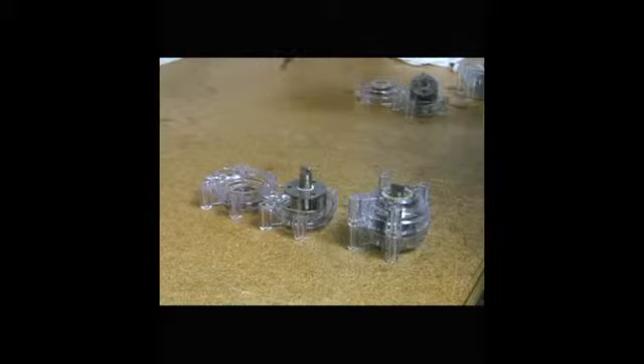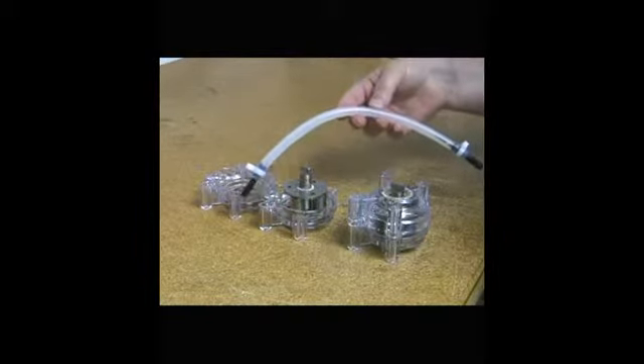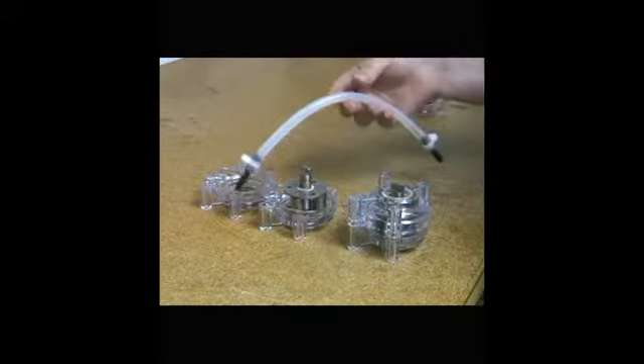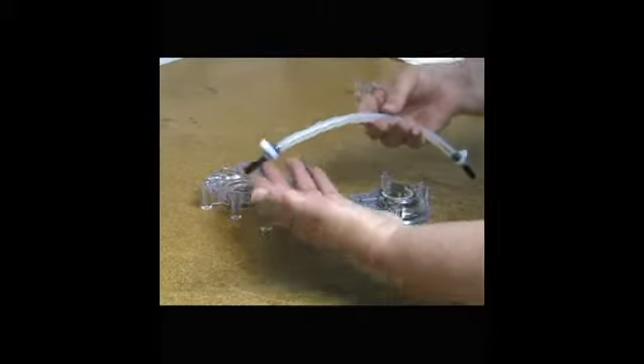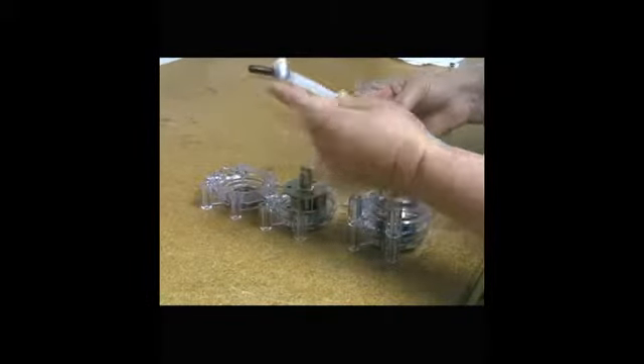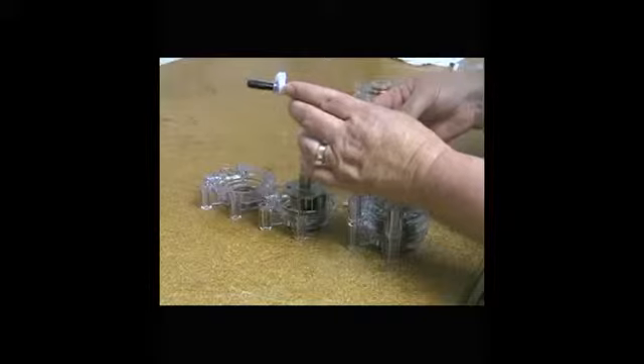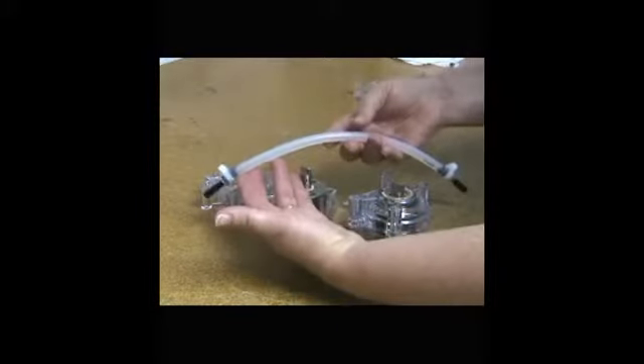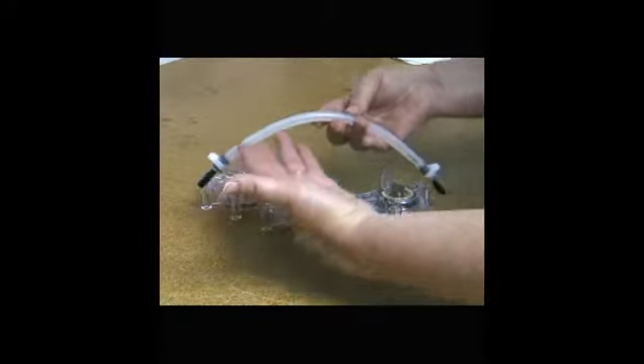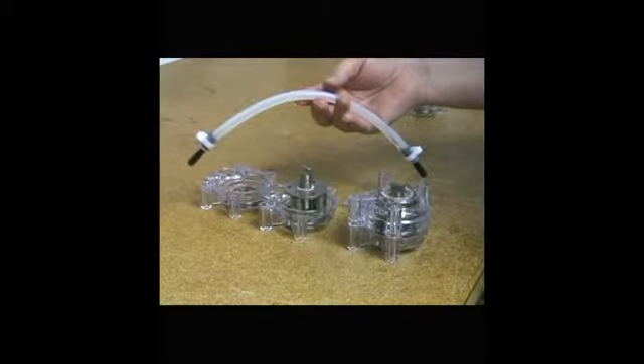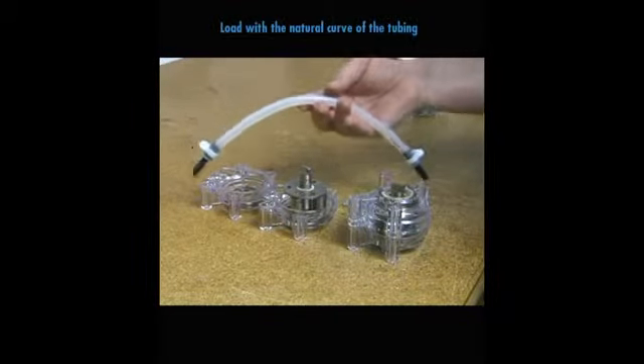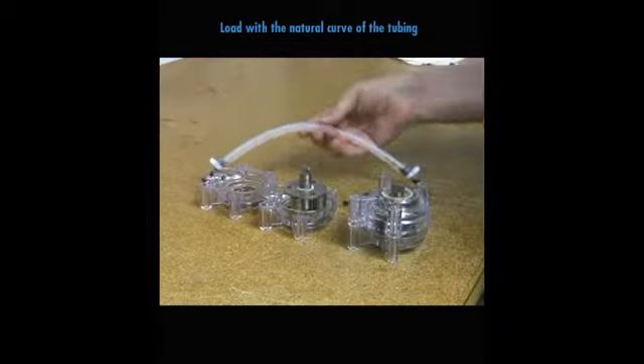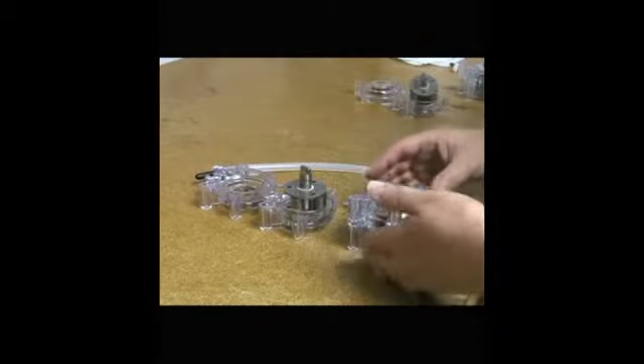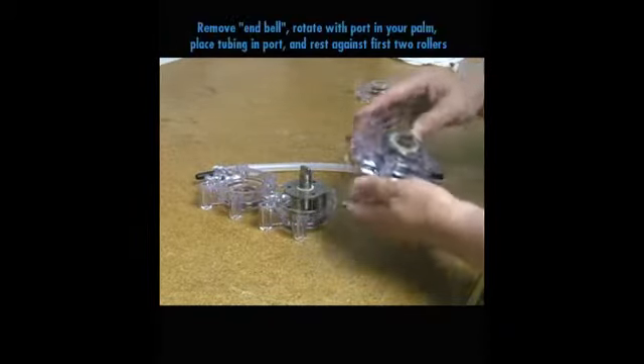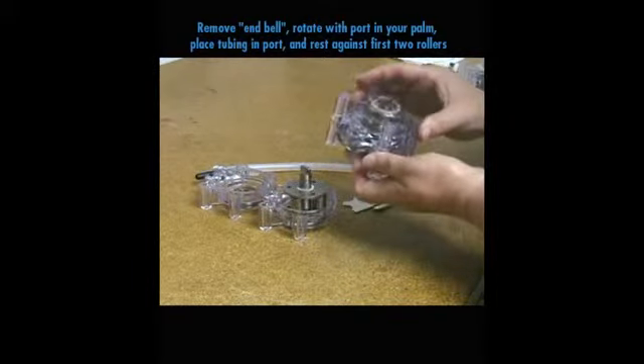First, you want to select a desired length of tubing that you're going to be placing into the pump. Insert tubing connectors and tubing clamps to hold the connectors in place. This is a silicone material. Notice how the tubing has a natural curve, and you're going to load this natural curve with the rotor. We're going to remove one of the end bells.